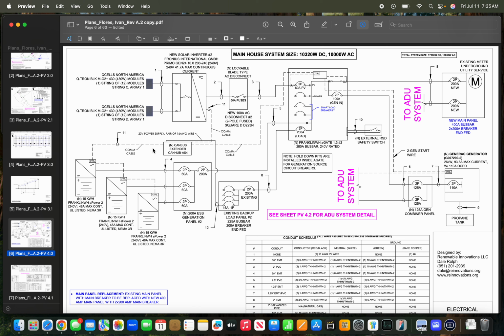You want to be looking and working with people that think about the little things, which I think about every little thing, even down to the wire, which the engineer and I had to go over some details on, and that led to some small changes. But we're dealing with some big wire because of voltage drop. We don't want voltage drop to be too significant because it can be a lot if we're dropping more than 1 or 2% over a 400-foot range. So we got it down to about 1.57, and hopefully that was based around 400 feet. I'm aiming for 350 feet to end up being the trenching distance, so that way we get closer to like 1.3, 1.2% in voltage drop, which is more than reasonable for the equipment.